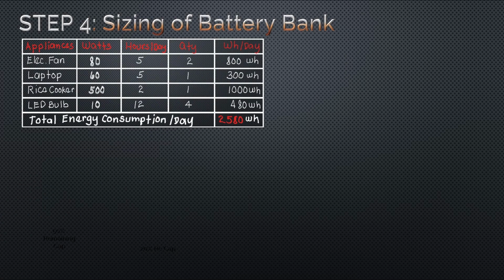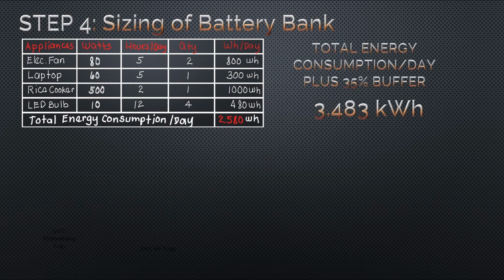So it is necessary to design the rating of the battery considering also the parameters we use in sizing the solar panels. So we need to use also the load profile. Now what are the other parameters we will consider? We also include a buffer to compensate for the system losses, and this is equal to 3.483 kWh. That is the total consumption per day plus 35%. Now, are those parameters enough to compute the size of the battery bank?